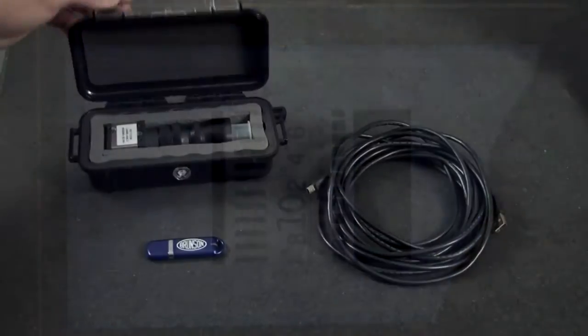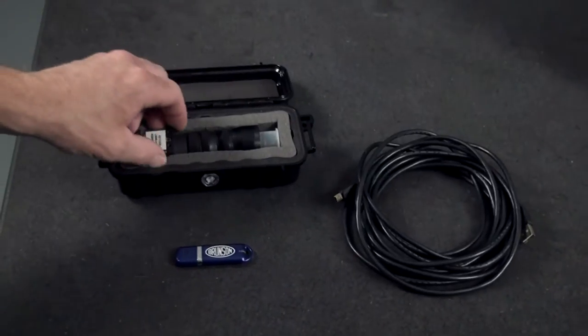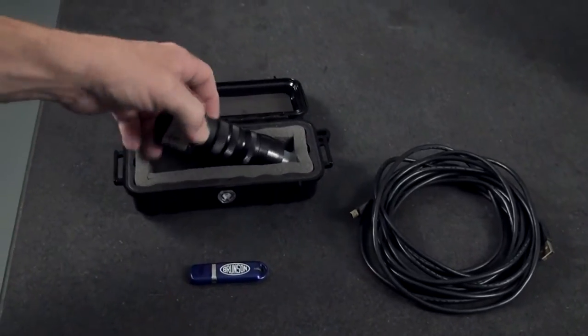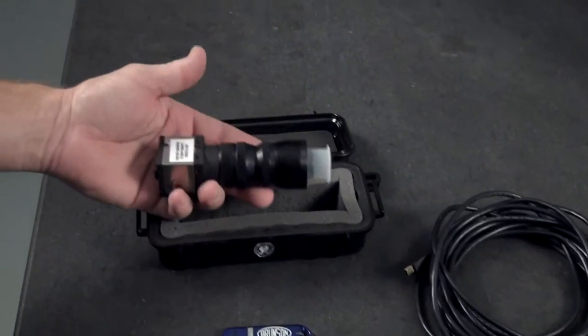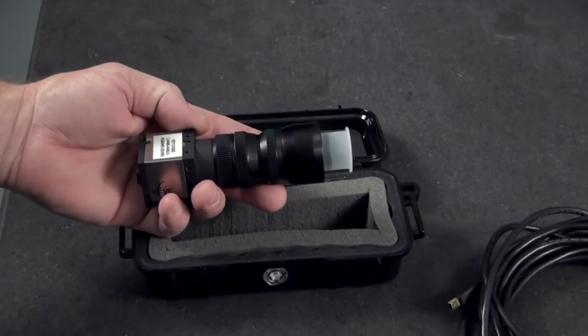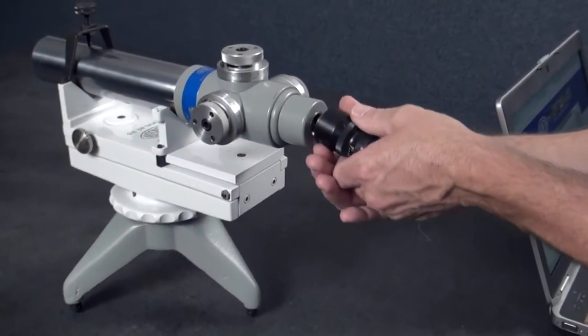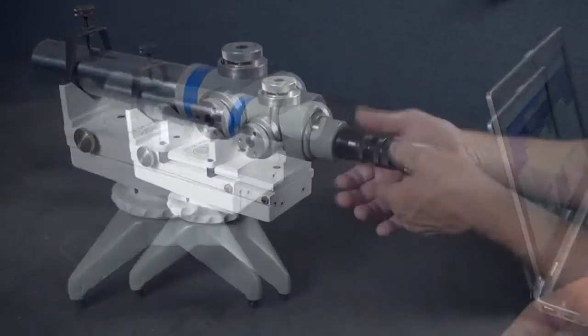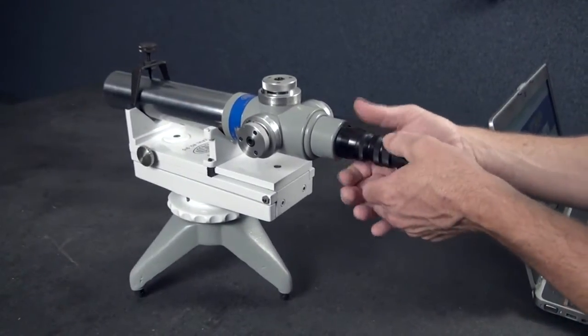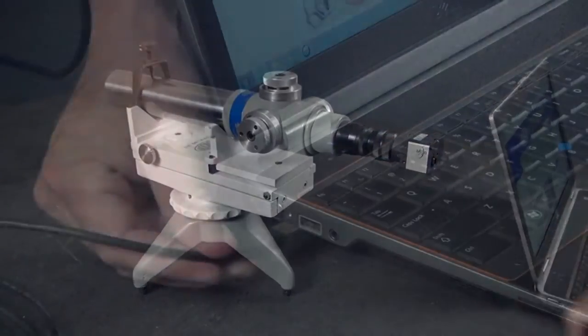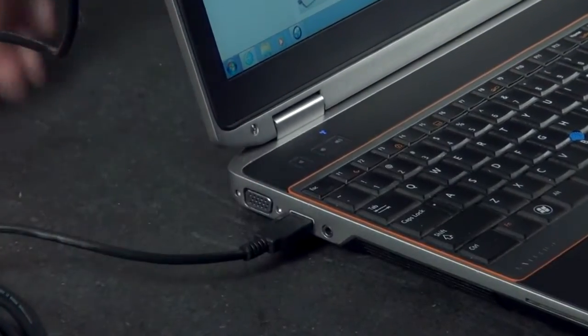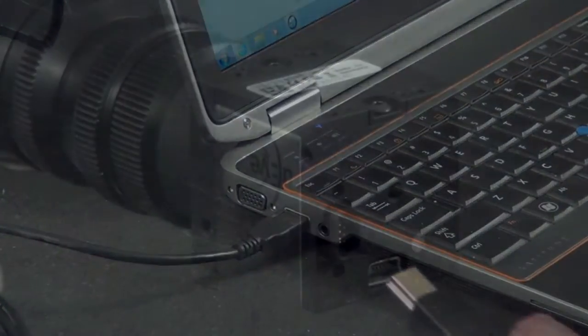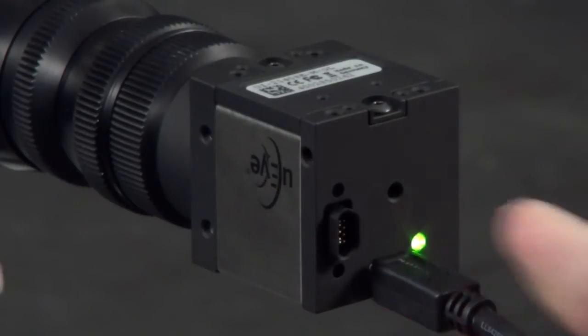The AlignCam is outfitted with a specially designed relay lens adapter for quick on-site user installation. To set up, the field technician simply connects the camera assembly to an optical instrument and plugs the USB cable into the camera and the computer. Power is supplied to the camera via the USB cable.